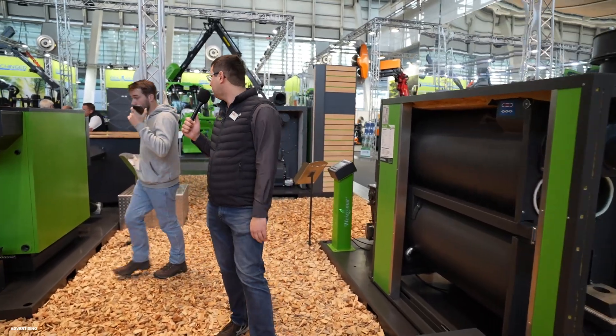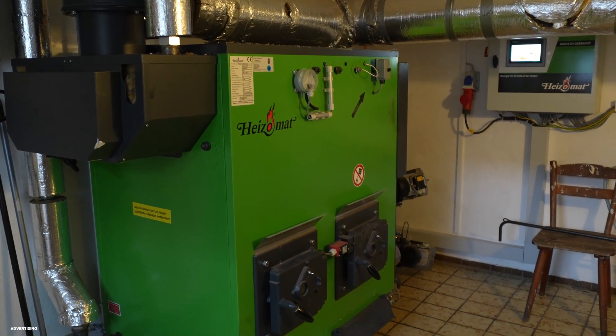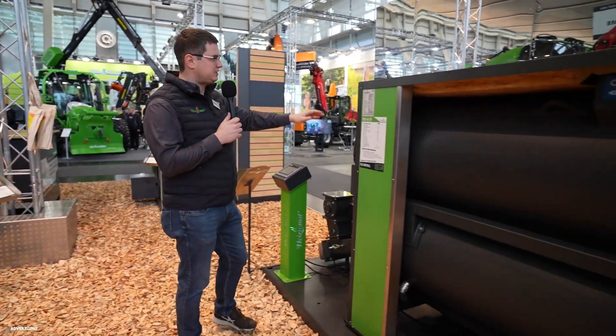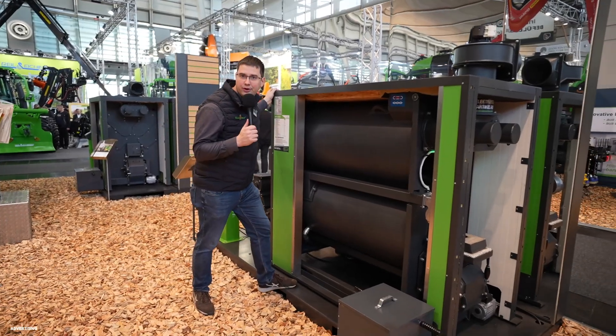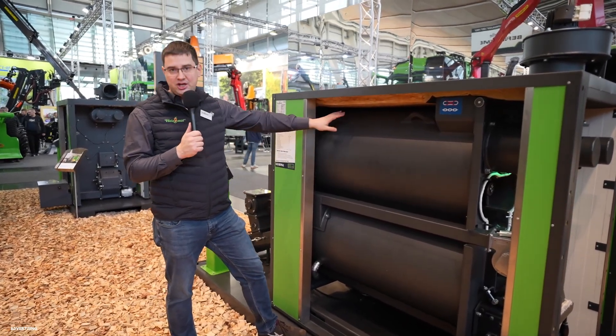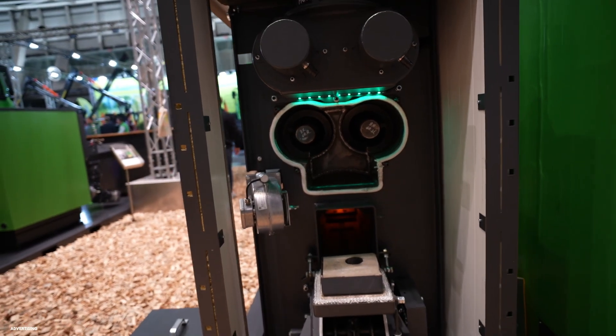We also have our boilers here. We start with our RA boiler, which is perfect for sawdust with combustion based on a combustion grate. Our second and main boiler system is the AK boiler — perfect if you burn wood chips that are a little dirtier, with more roadside residues or branches. As you know, the AK has an ash chain inside, so it doesn't matter if you have stones or nails in the wood chips — everything that goes in also comes out.